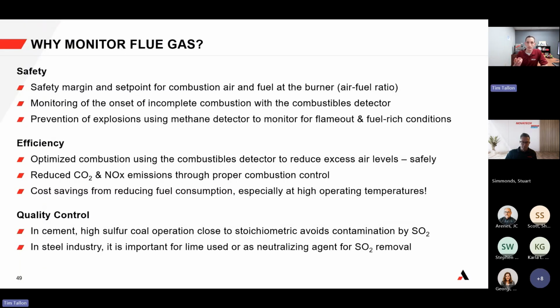Also, with a combustible measurement, you can monitor for combustible breakthrough. You can monitor for high combustibles. You can monitor for the risk of an unsafe condition with that combustible measurement, because as you start to see it increasing, that's a signal that something's happening, and above certain thresholds, action needs to be taken. And then also, we've seen with our standard WDG-V, but also just with the measurement of methane, preventing unsafe conditions, preventing fuel-rich conditions from flame out, in some cases tube leaks, or also just process-related issues. You can have a methane detector before an electrostatic precipitator to reduce the risk of explosion, because you can monitor for methane and other hydrocarbons without it getting to that point of the electrostatic precipitator.